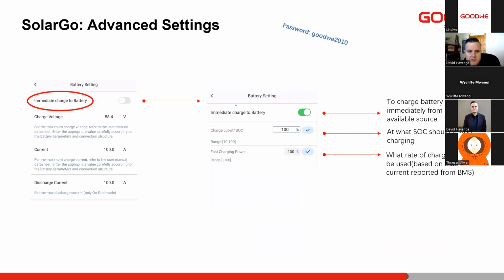As I mentioned, that immediate charge battery settings, you can set the cutoff. So if we only want to charge a battery to 50%, we can also set the amount of power to charge the battery. So if you want to slowly charge or charge very fast, you can select the percentage of the charge rate, so the maximum rate based on the BMS, and then at what SOC we should stop charging. So this will charge the battery. Once it hits the cutoff SOC, this will go off again.